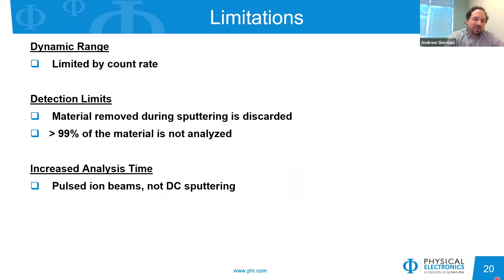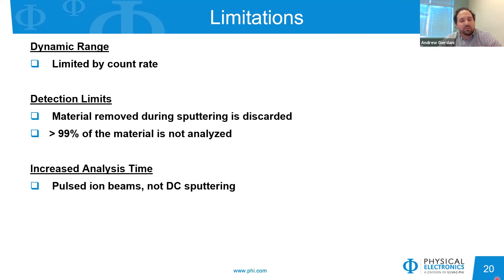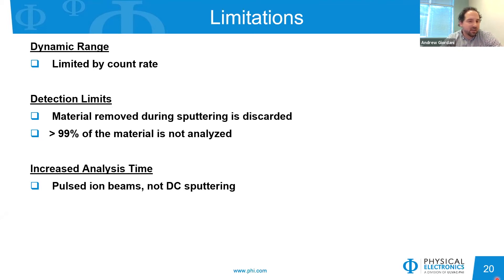Despite its advantages, TOF-SIMS has some limitations compared to quadrupole or magnetic sector depth profiling. Dynamic range is limited by the count rate, making six orders of dynamic range very difficult to achieve. Detection limits are also limited because 99% of the material being removed is not analyzed — each sputter event discards that material, unlike a DC beam where sputter and analysis beams are the same and you're looking at everything coming off one species at a time. Analysis time is increased because you're switching between pulsed beams rather than using a DC beam.